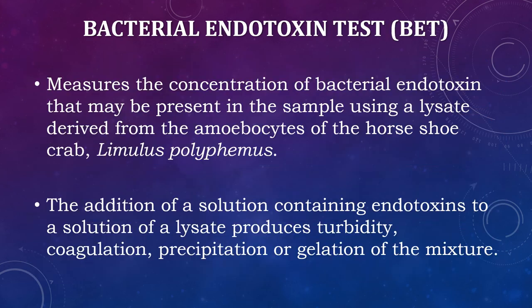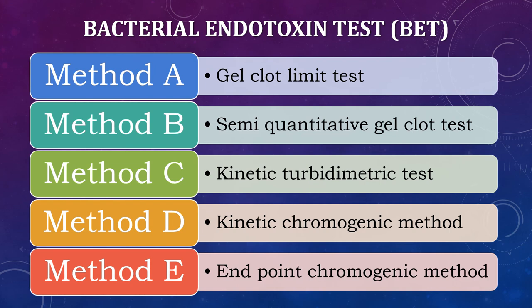The bacterial endotoxin test measures the concentration of bacterial endotoxin that may be present in the sample using a lysate derived from the amoebocyte of the horseshoe crab, i.e., Limulus polyphemus. The addition of a solution containing endotoxins to a solution of the lysate produces turbidity, coagulation, precipitation, or gelation of the mixture. Different methods are used to test bacterial endotoxin: gel clot limit test, semi-quantitative gel clot test, kinetic turbidimetry test, kinetic chromogenic method, and endpoint chromogenic method. With these methods, you can quantify the bacterial endotoxin presence inside the sample.